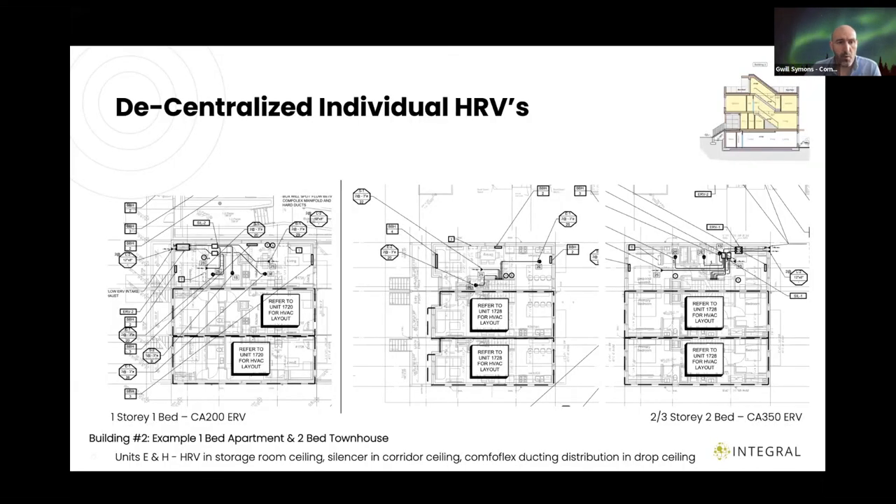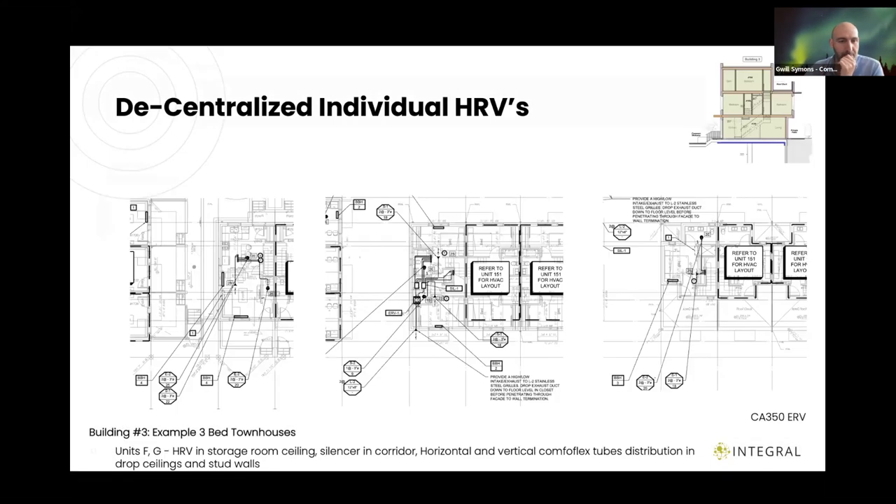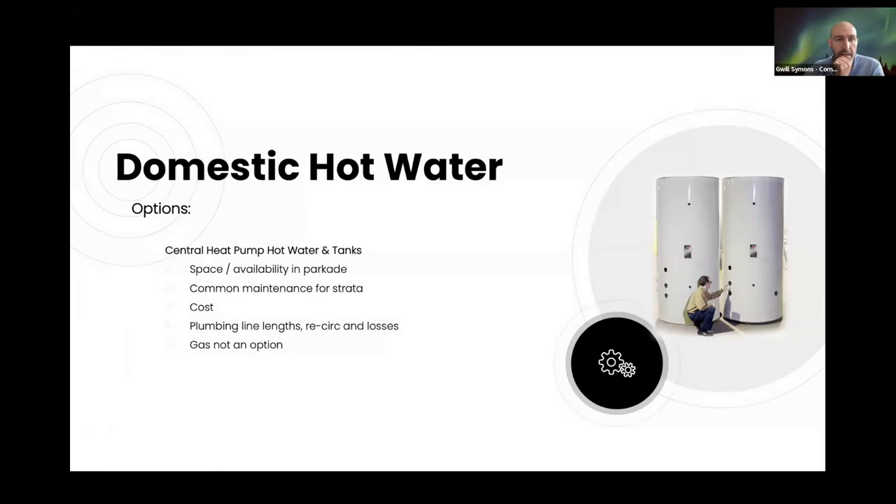For Building 2's level one one-bed apartments and three-storey townhouses, the same setup applies — HRV in the closet in the bedroom with a short run to the outside. In the townhouse, there's debate about whether ComfoFlex pipes fit in a two-by-four wall or need two-by-six — some say yes, some say no. In other unit layouts, the HRV is located on the middle floor and distributes up and down for the shortest possible runs.